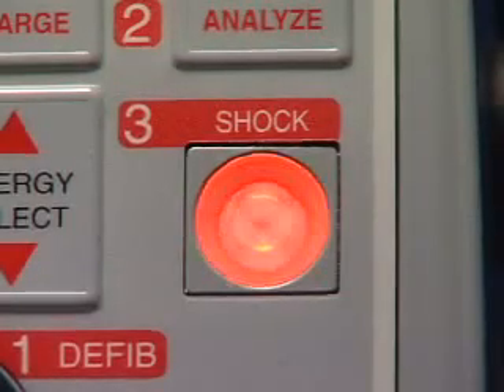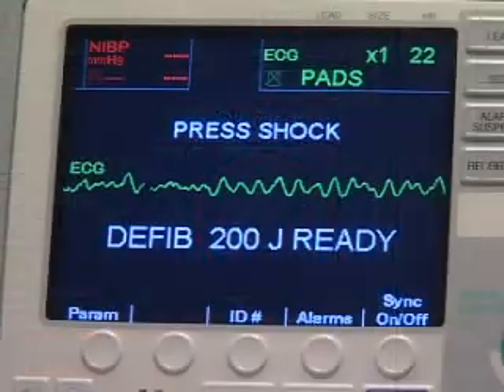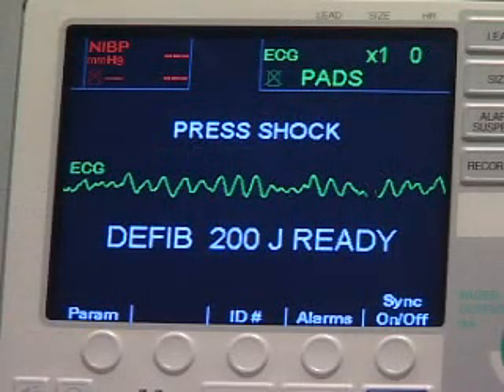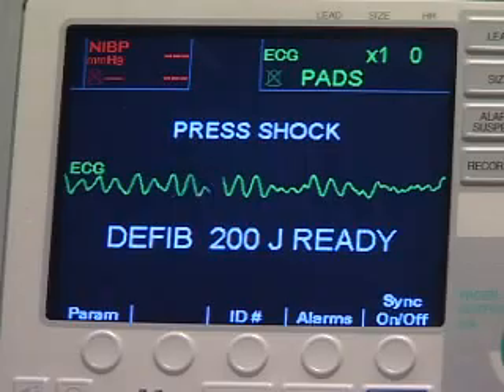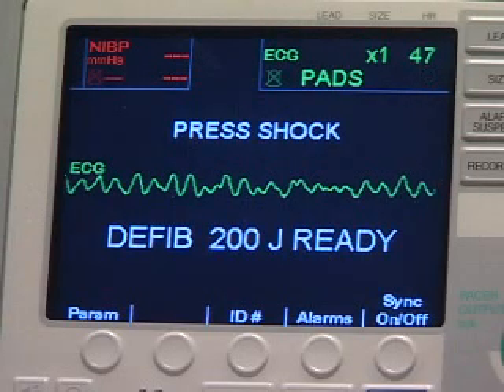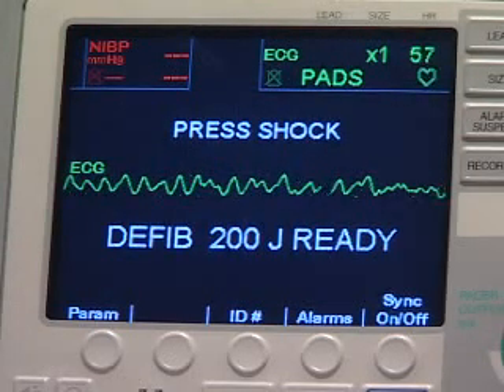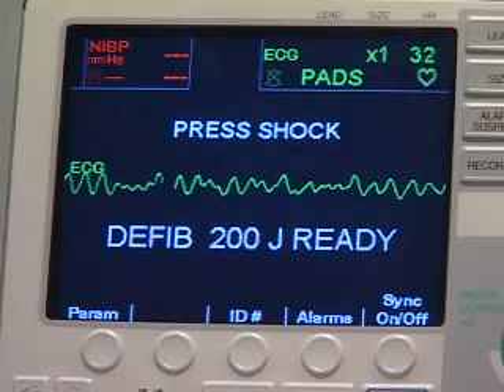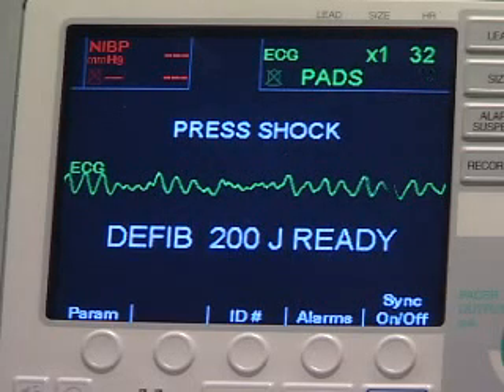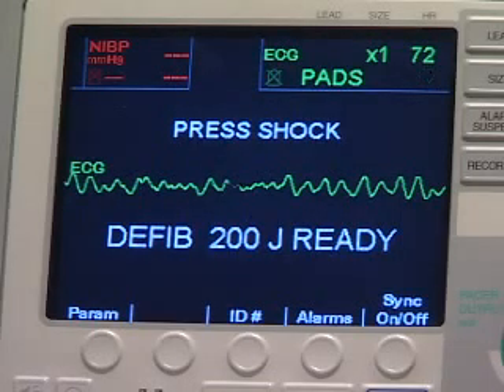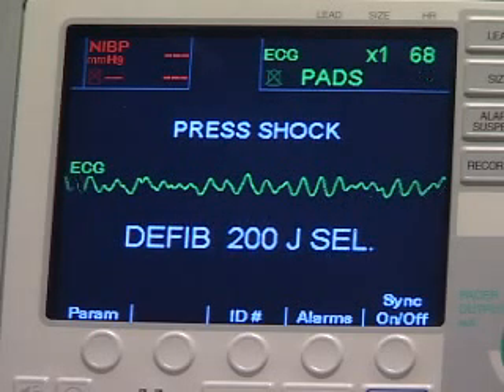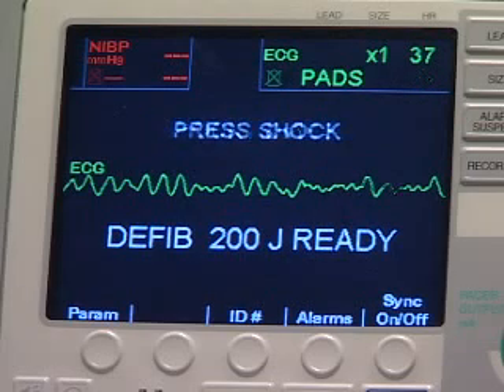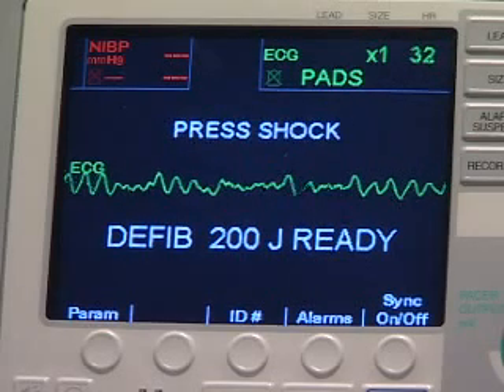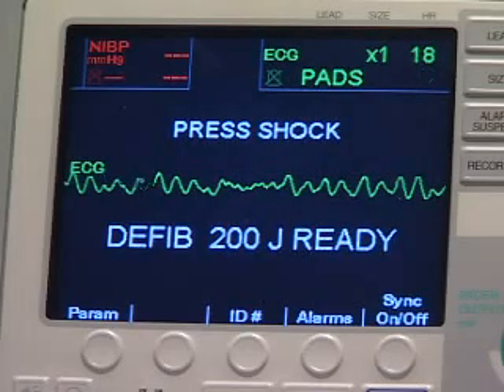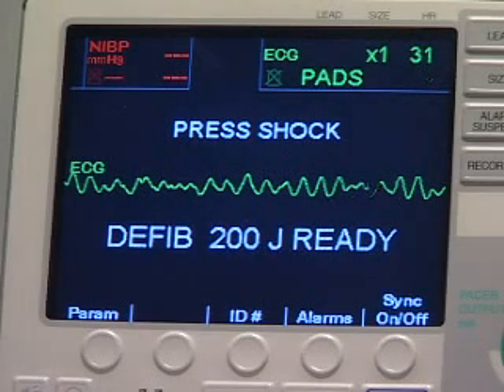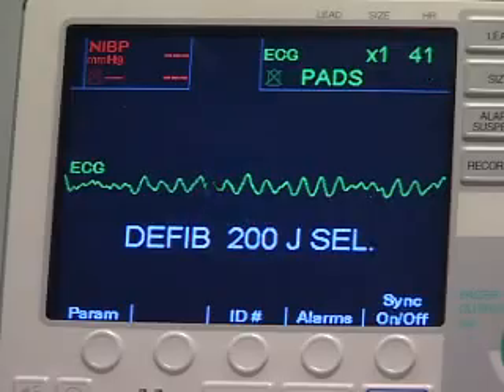When the unit is charged and ready, the shock button will illuminate and the Press Shock message and voice prompt will be issued. Press shock. On the AED version, a continuous tone will sound for 10 seconds, followed by an intermittent beeping for 5 seconds. The shock must be delivered within this 15-second interval, or the defibrillator will disarm. On the manual version, a continuous tone will sound for 50 seconds, followed by an intermittent beeping for 10 seconds. The shock must be delivered within the 60-second interval, or the defibrillator will disarm.